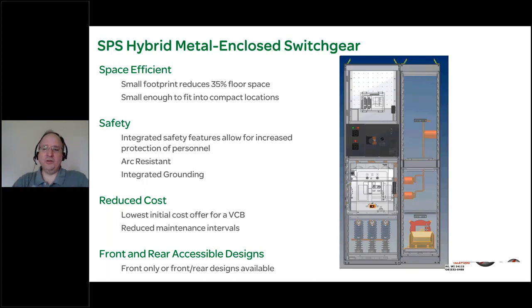And I have to be honest with you, when Europeans come over here and see Americans on new equipment going through that process, which A, is considered an exposed energized task by NFPA 70E, and B, is very hot, difficult, and time consuming, they think we're barbarians. For the last 20 plus years, integrated grounding has been a requirement in similar new equipment in the IEC world, which governs almost every country on our planet other than Canada and the United States.